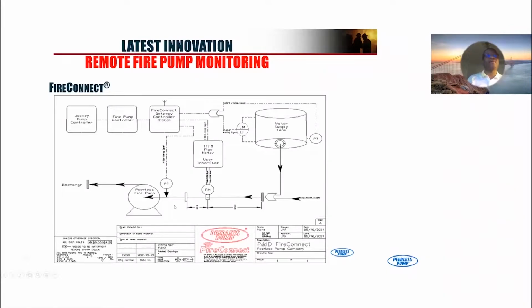So here you're looking at a schematic of a standard fire pump. You have your water supply coming into it. With this device, you need a flow meter at the suction side, with a minimum of 5 straight pipe runs before the flow meter and 2 straight pipe runs before your isolation valve. You will need a gateway - Fire Connect has its own controller, like a control panel, that communicates to the cloud. Everything is communicated to the cloud. From your jockey controller and fire pump controller, there's an option to wire directly into the gateway, and you also have a pressure transducer on the suction side for information, plus one on the water tank to give you level readings. It's a fairly simple device to install, but let's get into what it actually does.